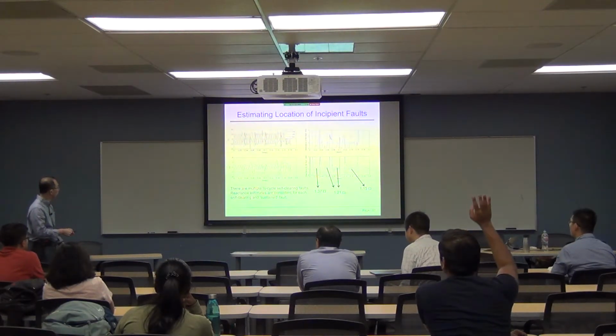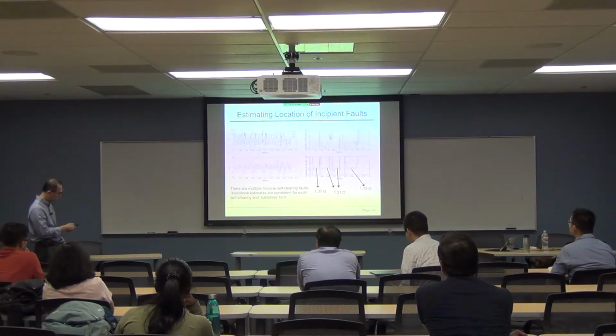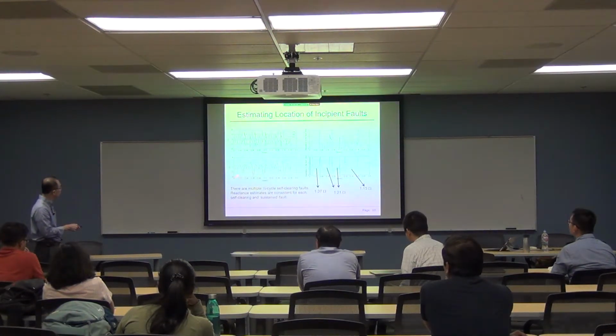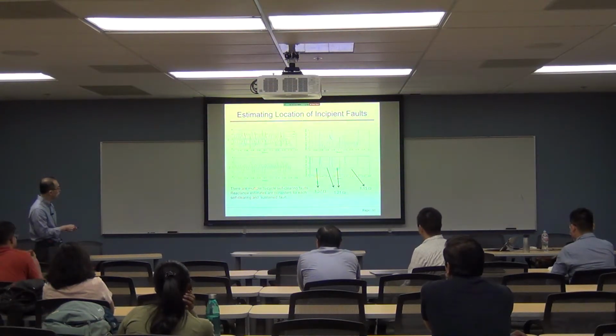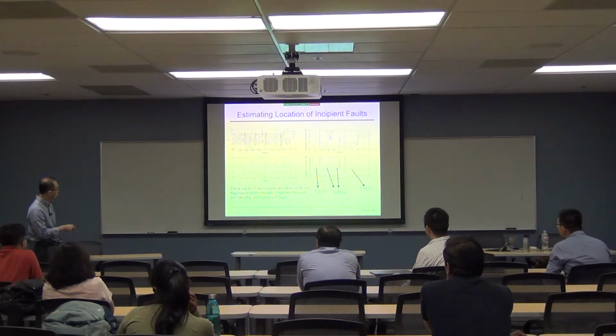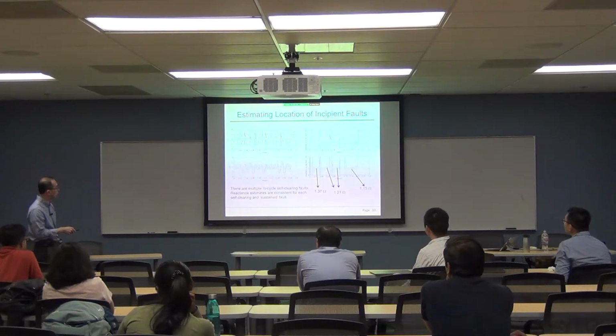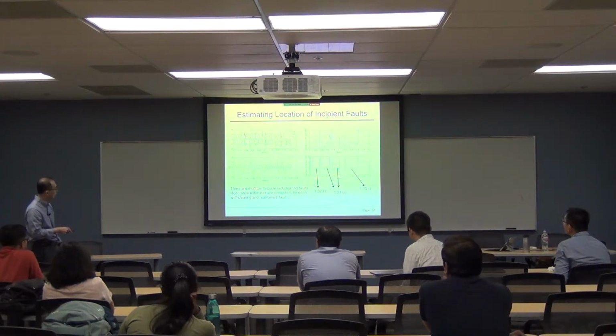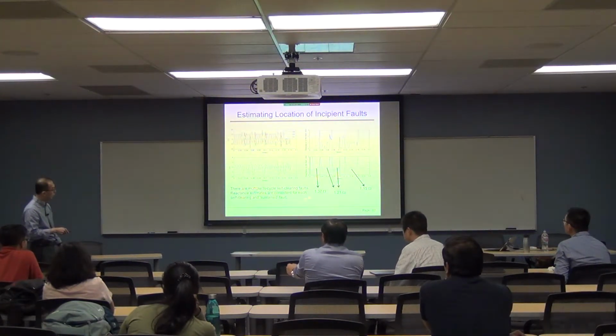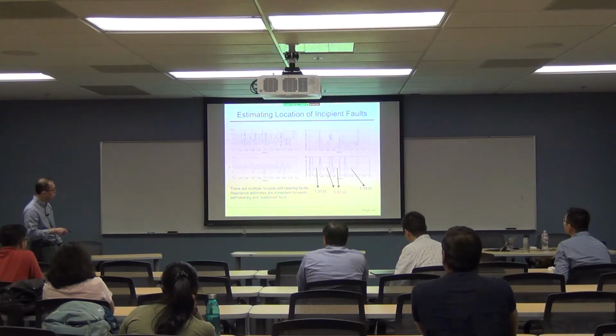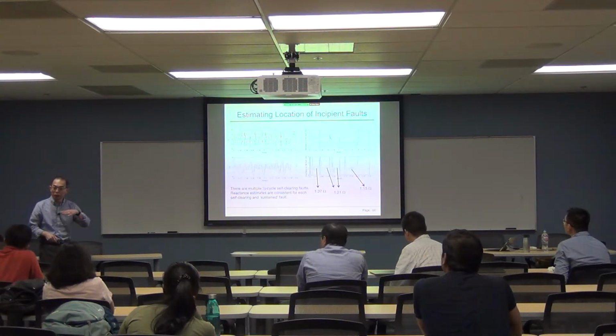In this particular case, you can see the incipient faults happen very quickly, right here, right here, right here, and then it turns into a full-blown fault right here. Using this approach, we were able to estimate that the fault location is actually at 1.38, 1.2, 1.15. So it is pretty stable.